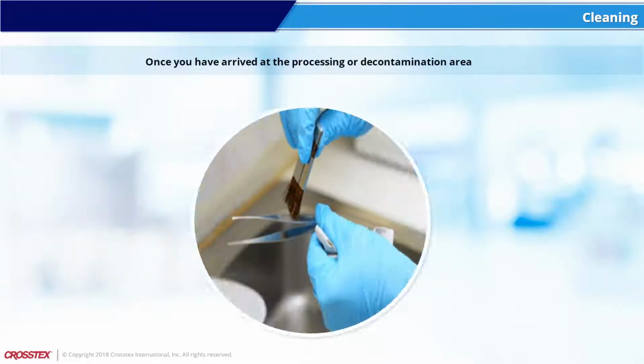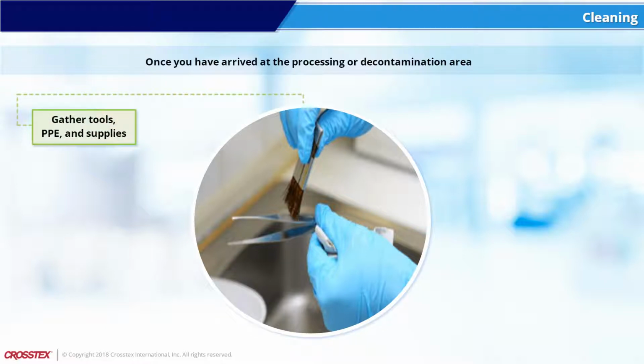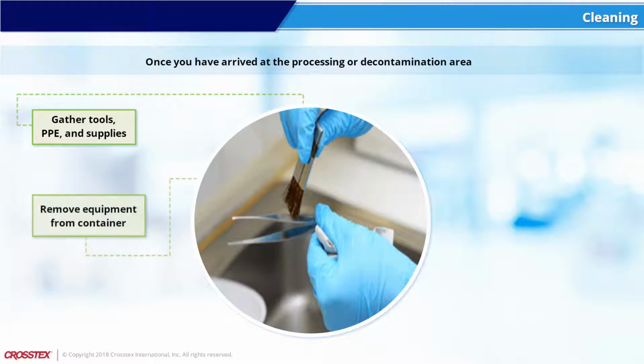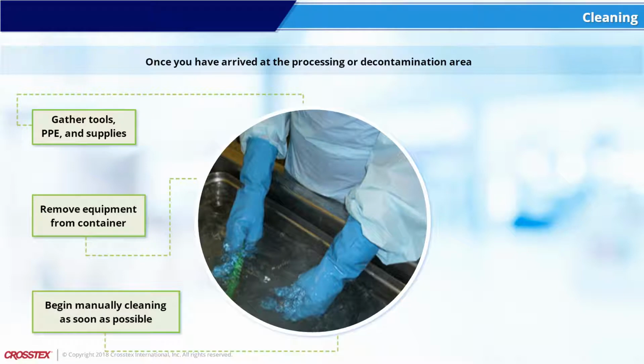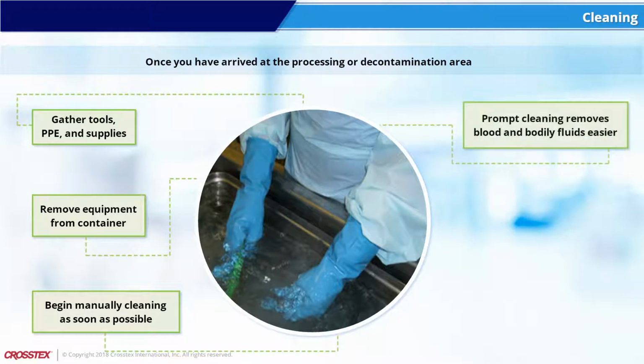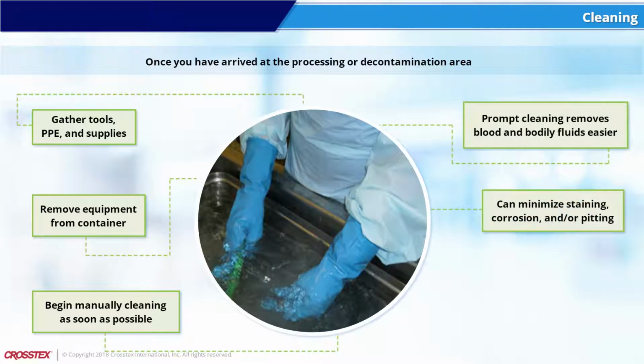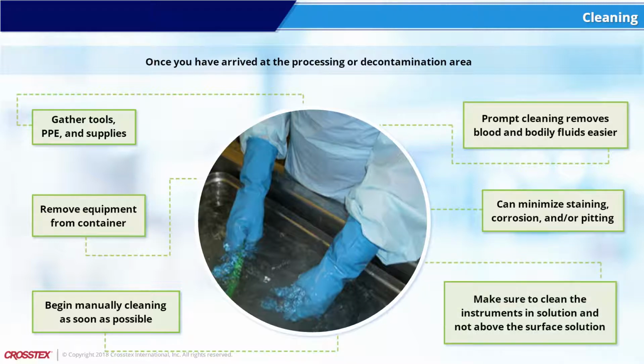Cleaning. Once you've arrived at the processing or decontamination area, it is important to gather any tools, personal protective equipment, and supplies prior to opening the container holding the contaminated equipment. While wearing appropriate PPE, remove the equipment from the container and place it in the designated area. Begin by manually or mechanically cleaning the soiled instruments as soon as possible. Prompt cleaning removes blood and bodily fluids much easier and can minimize staining, corrosion, and/or pitting. It's important to clean instruments in solution and not above solution surface.